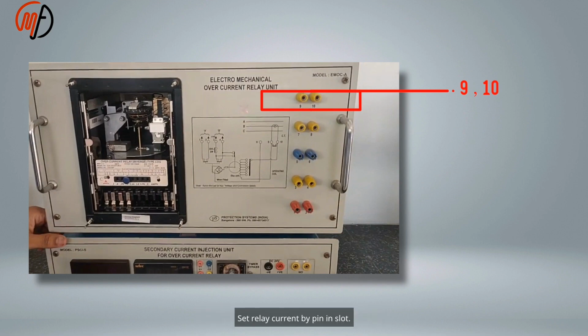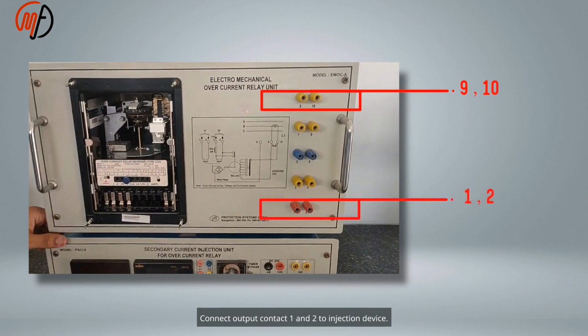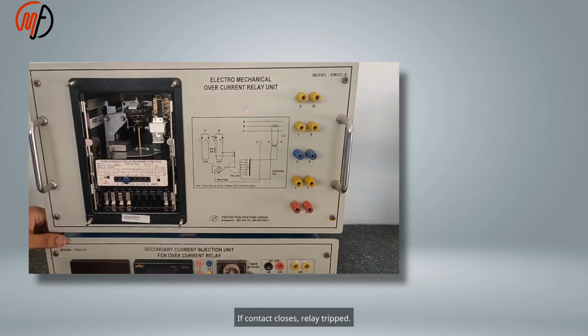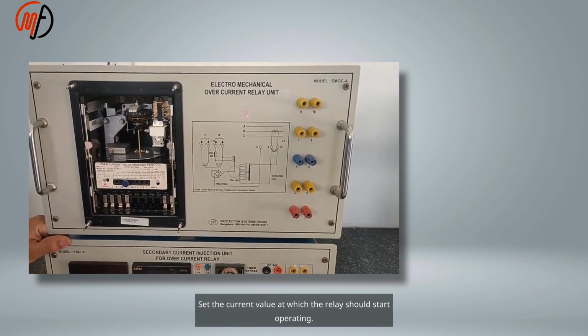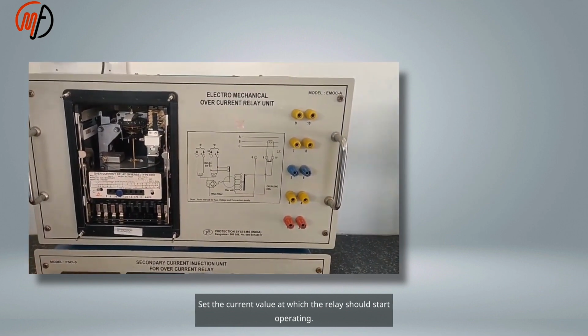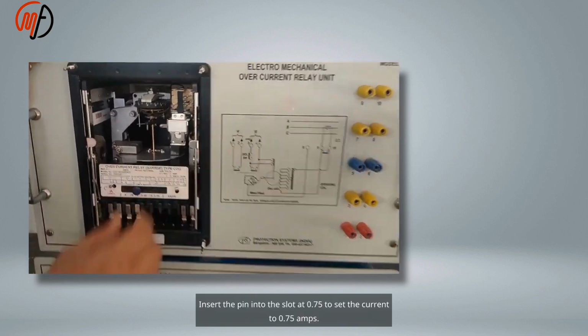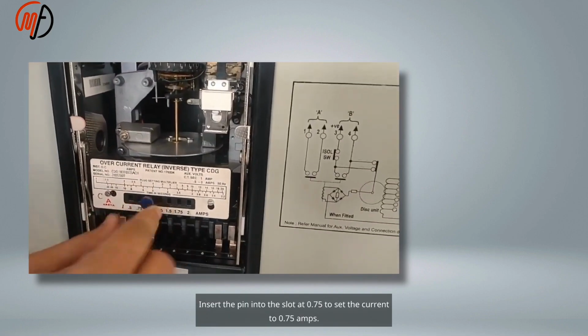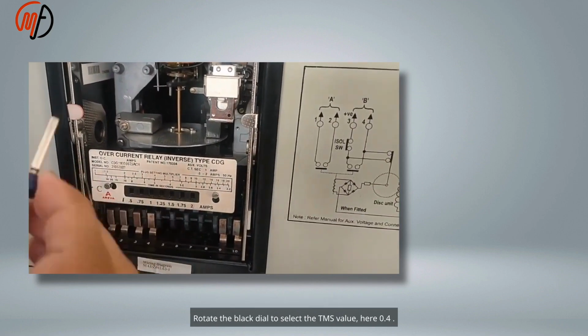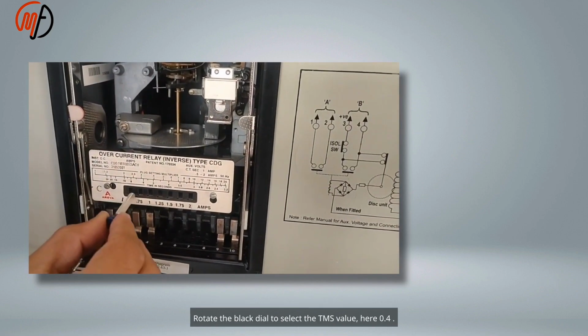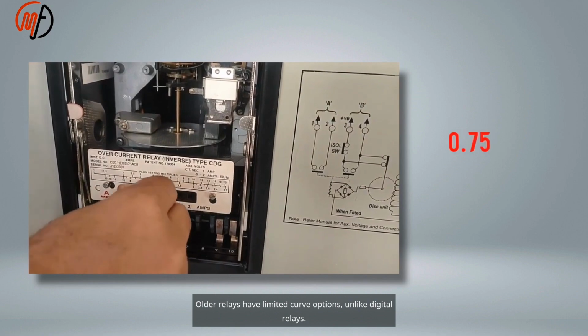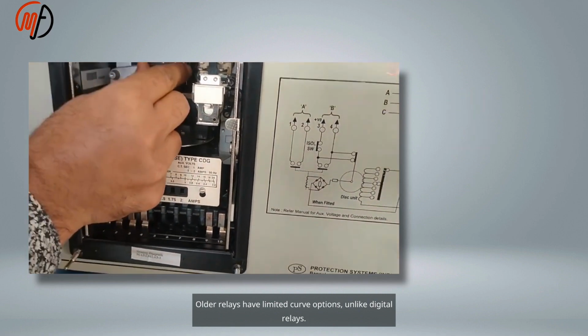Set the relay current by placing the pin in the slot. Insert it at 0.75 for 0.75 amps. Choose the TMS by dial; select 0.4 for the line. Set the current value at which the relay should start operating. Insert the pin into the slot at 0.75 to set the current to 0.75 amps. Rotate the black dial to select the TMS value, here 0.4. Older relays have limited curve options, unlike digital relays.